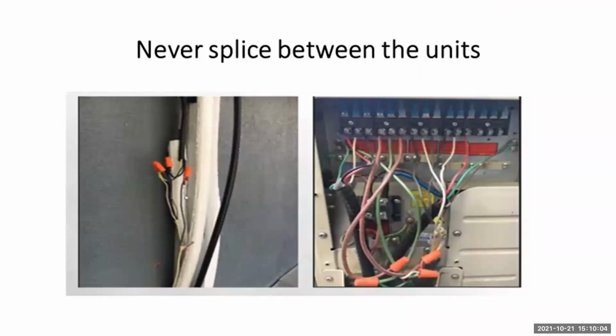Do not ever splice wires. Never use solid core wire. Always use shielded stranded 14 gauge unless the installation manual calls out for a larger wire to be used, and that would only happen if it's an extremely long run. So always refer to your installation manuals when you're questioning that.